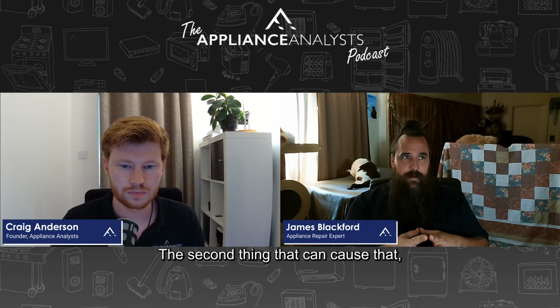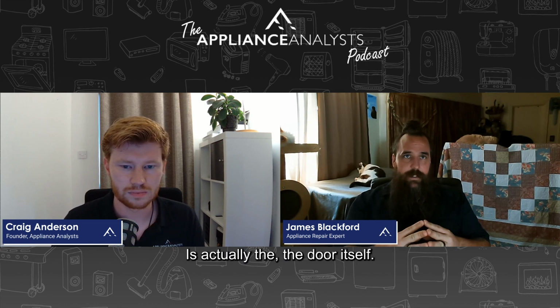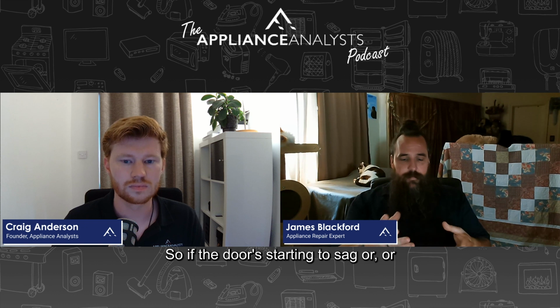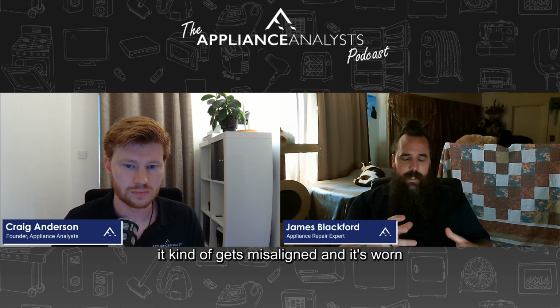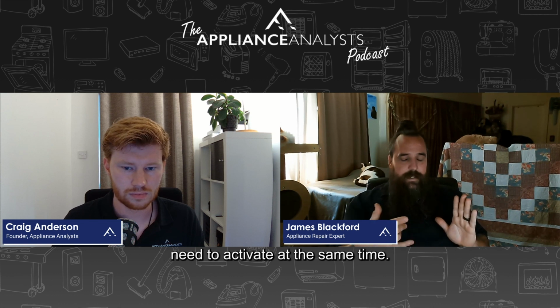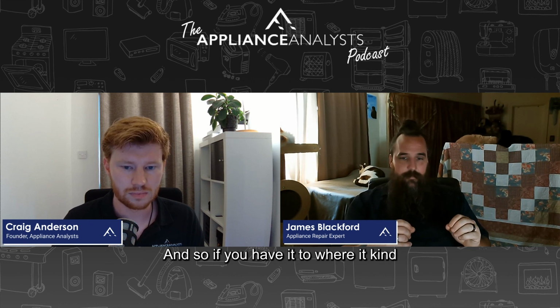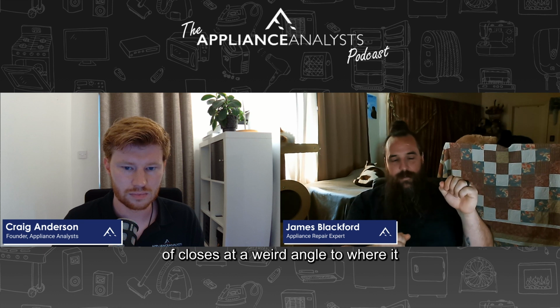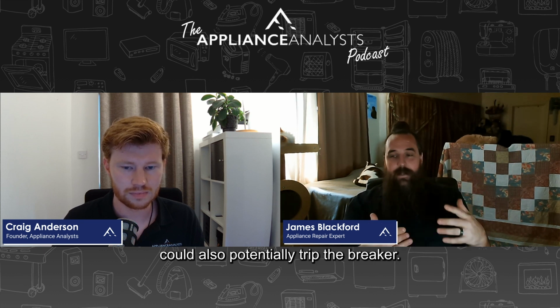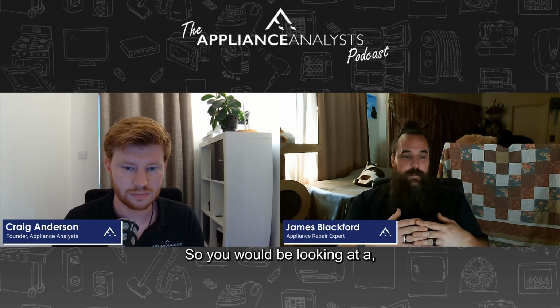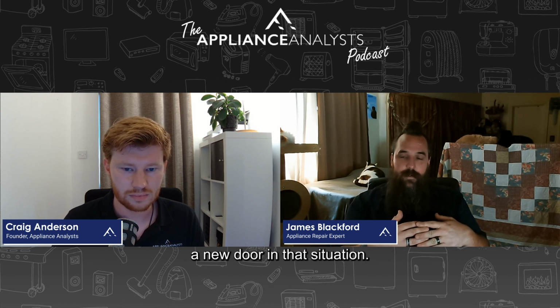The second thing that can cause that is actually the door itself. If the door is starting to sag or gets misaligned and worn out, when you shut the door, the switches need to activate at the same time. And if it closes at a weird angle to where it activates one switch but not 2, that could also potentially trip the breaker. So you would be looking at a new door in that situation.